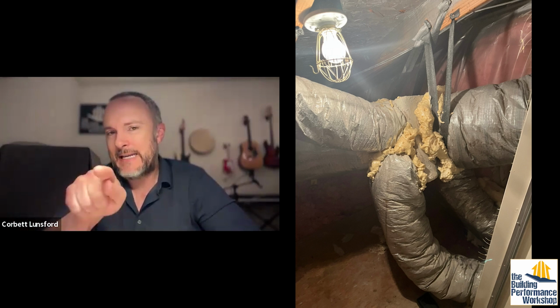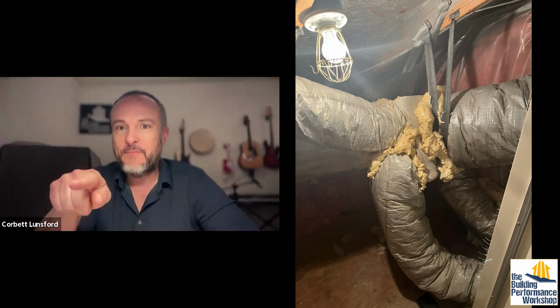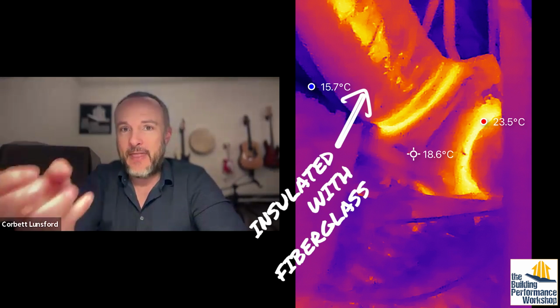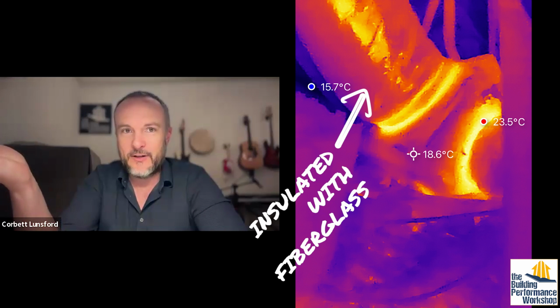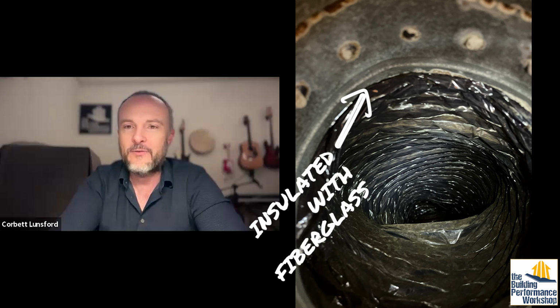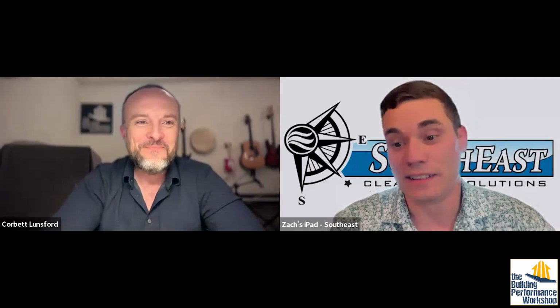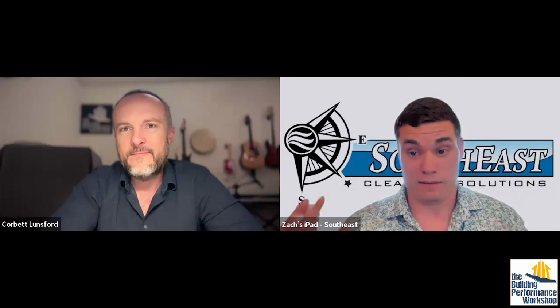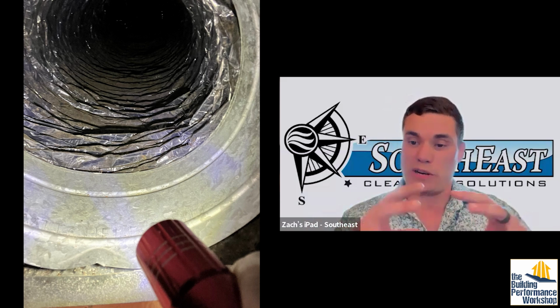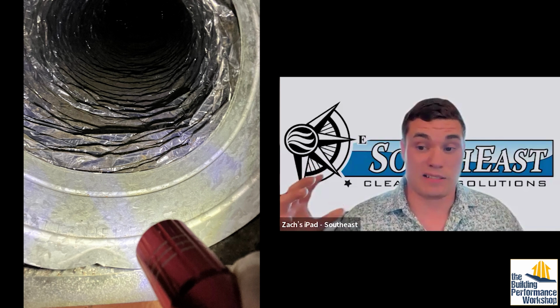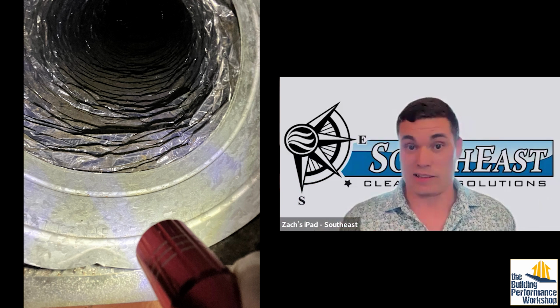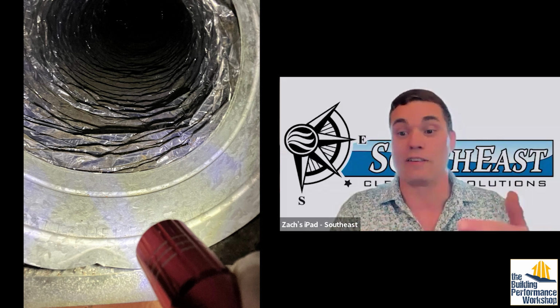And to be perfectly clear with everybody who does not understand how this stuff works, what is behind that plastic mylar duct, if you tear it, is fiberglass. That can then get into your airstream, and then you've got fiberglass floating around inside your house, which is generally not what we are looking for when you're trying to make the house better, more healthy. So you really would want to pull that duct nice and tight. What happens when you have it nice and straight and tight, you get a lot less dust that sticks in there. As it sits in that photo, that's like speed bumps for the air and for the dust to collect.